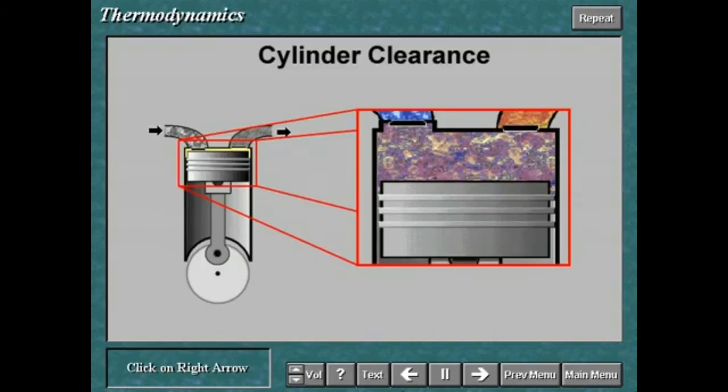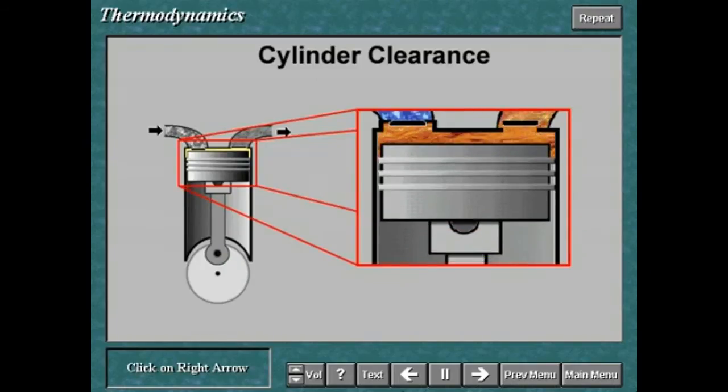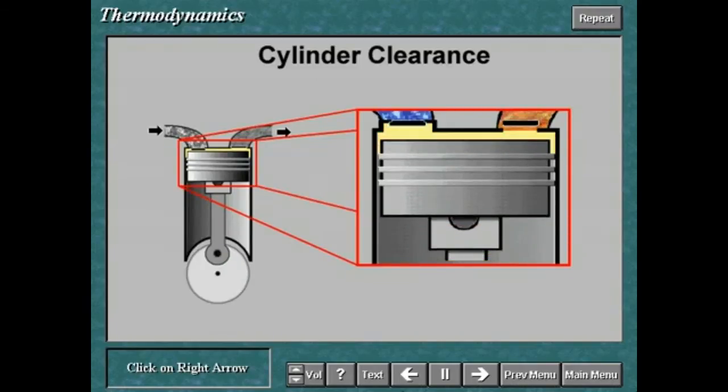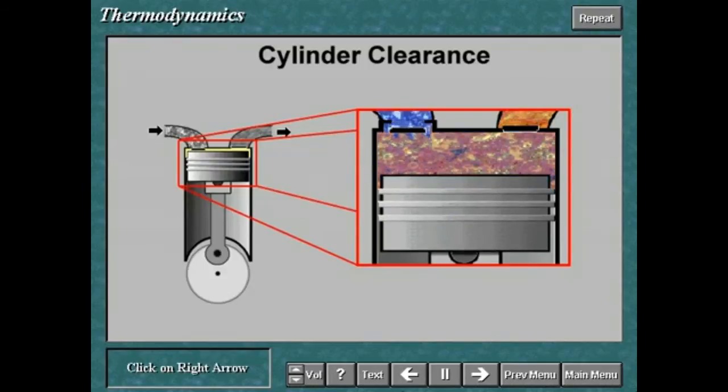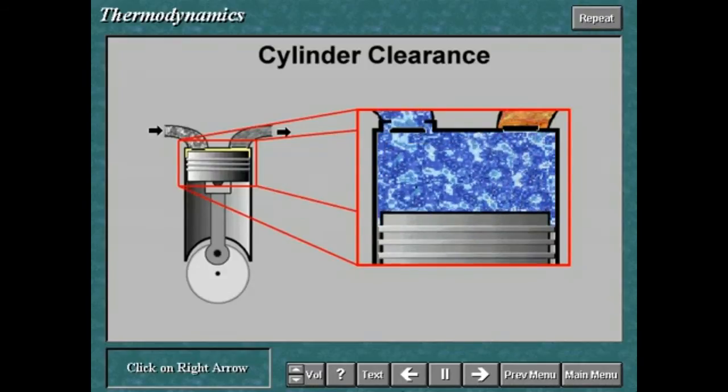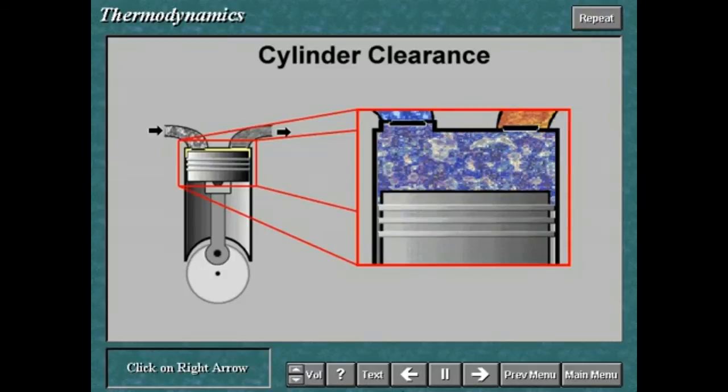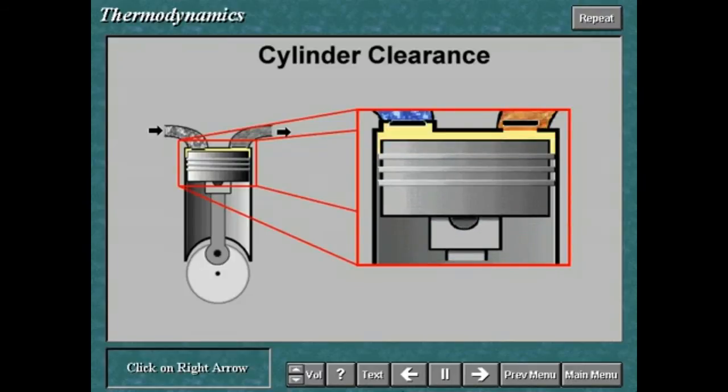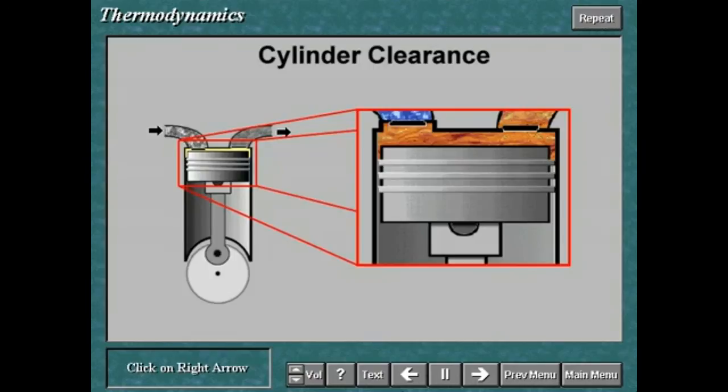Due to cylinder clearance, a certain amount of gas remains trapped within the cylinder at the end of the compression stroke. This gas is under discharge pressure and temperature. The subsequent suction phase can only begin when this remaining gas has re-expanded to pressure P sub A.